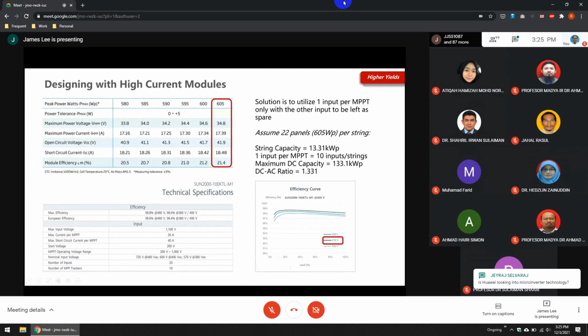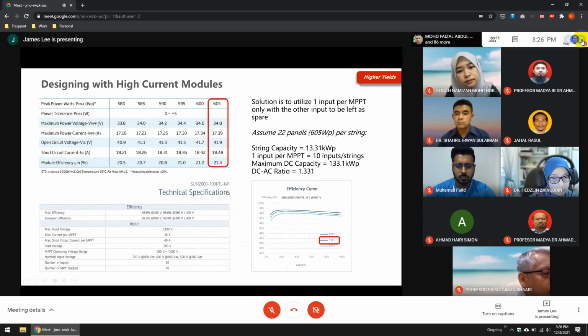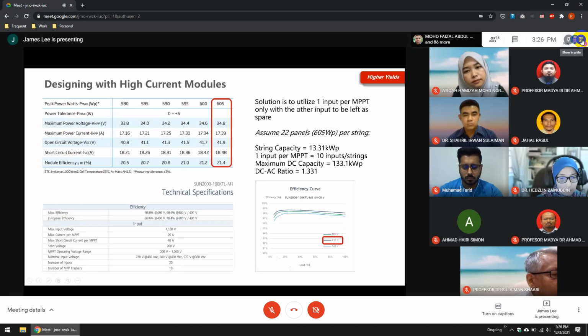Our maximum current per MPPT is 26 amps, and our maximum short circuit current per MPPT is 40 amps. So our operating current is already well above the panel's for a single string, and our ISC is also well above it. This works because instead of using all the inputs per MPPT, you only need to use one input per MPPT to solve that issue.